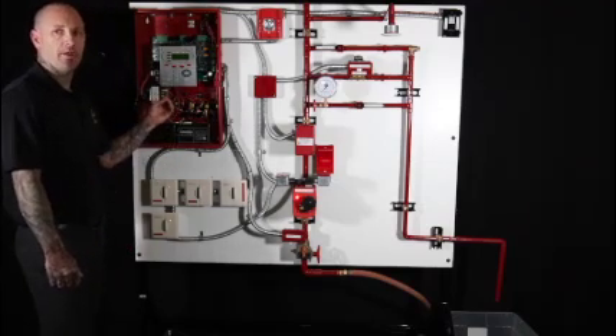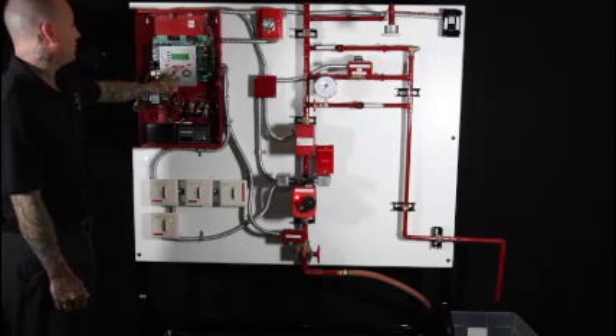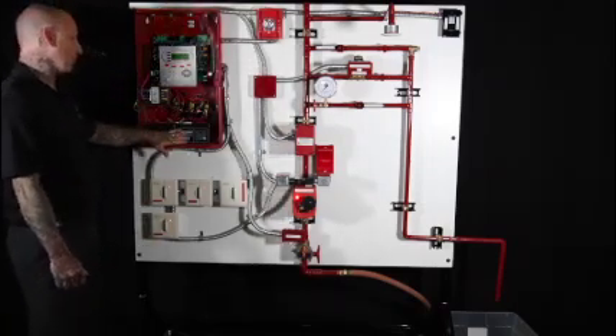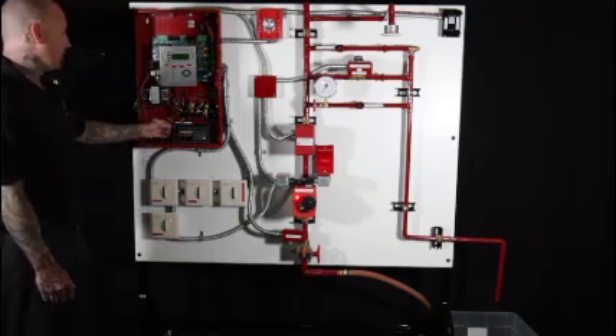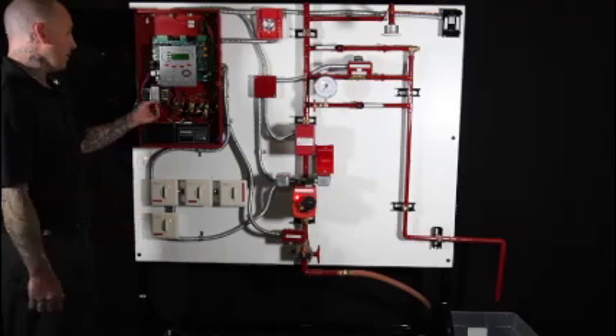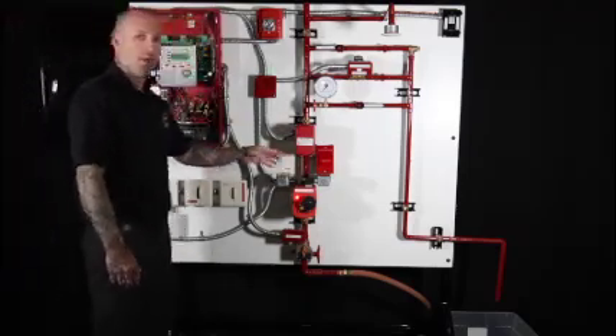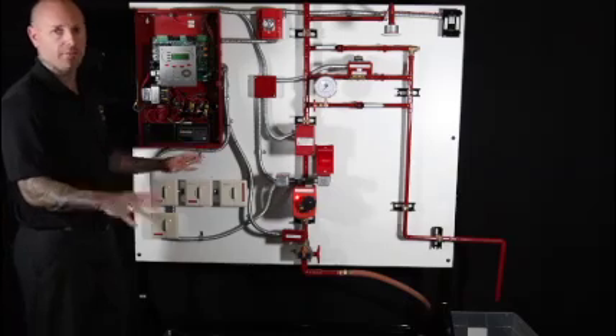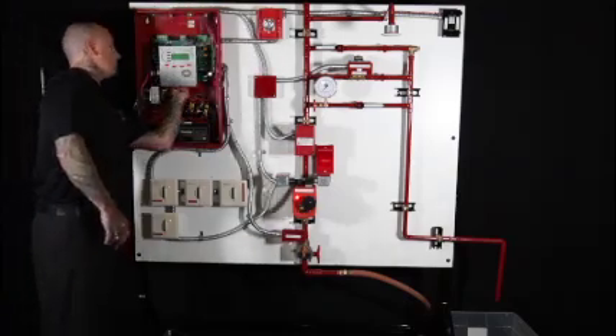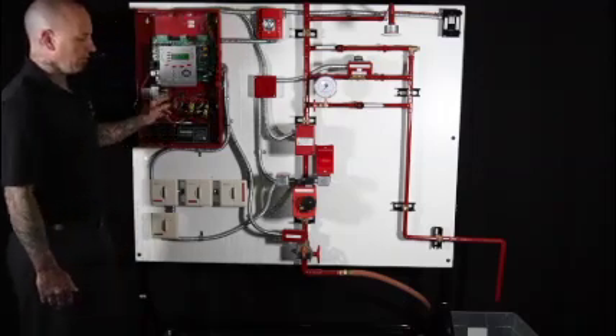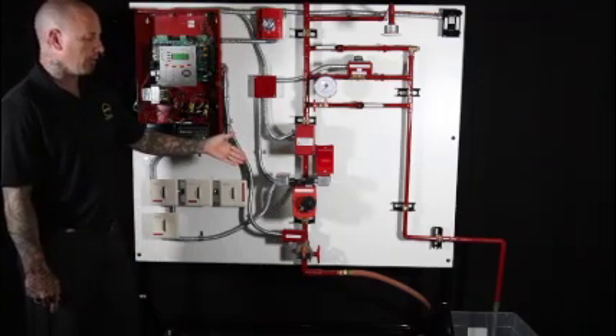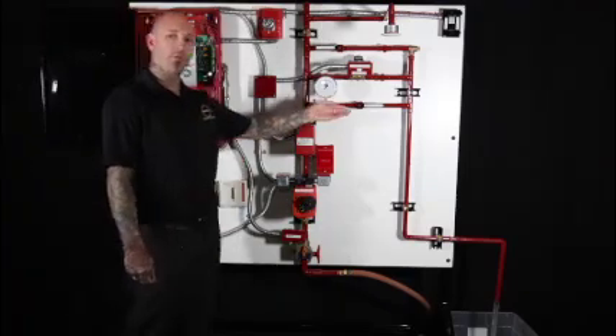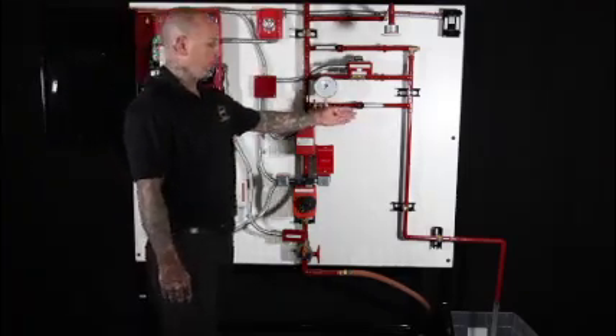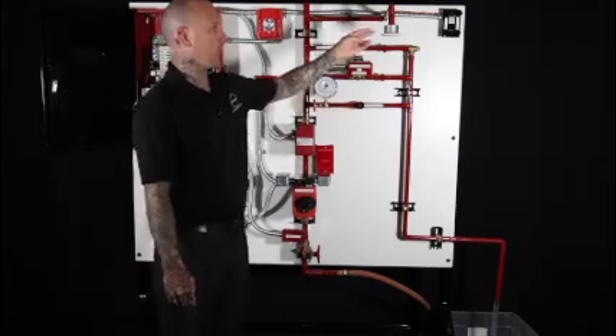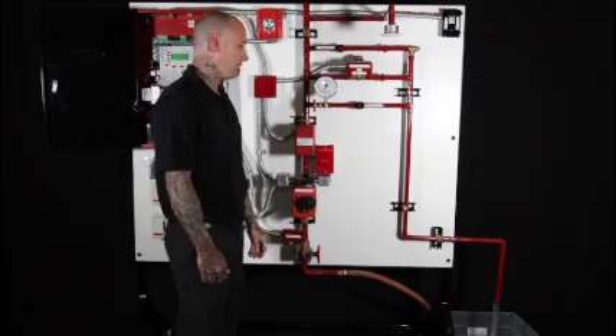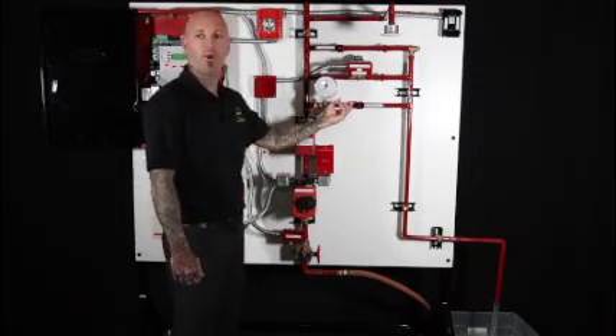As that alarm comes into the panel, we'll silence it, and in 24 hours you have your batteries for your backup supply. As soon as you lose battery backup power, the system will detect complete loss of power and turn the system all back on by itself. You lose power, and the system turns back on, flowing water through the broken sprinkler pipe you already had, or the open sprinkler pipe and sprinkler head you may have now. At this time, I'll have to shut the water off manually again.